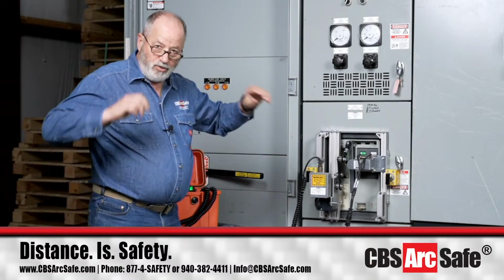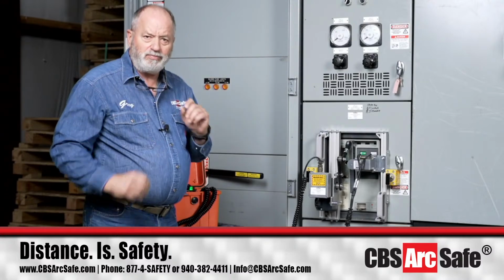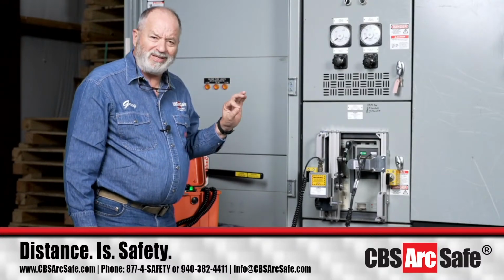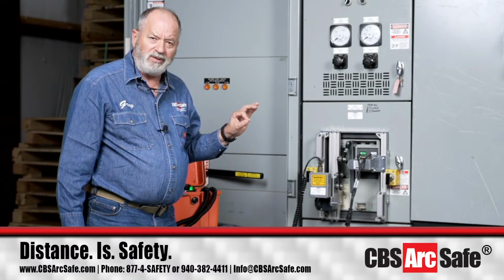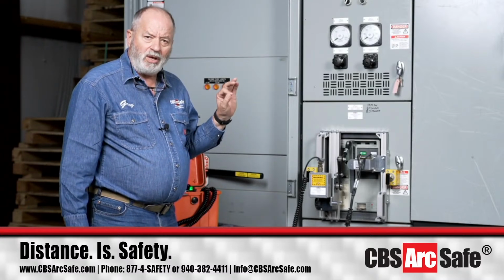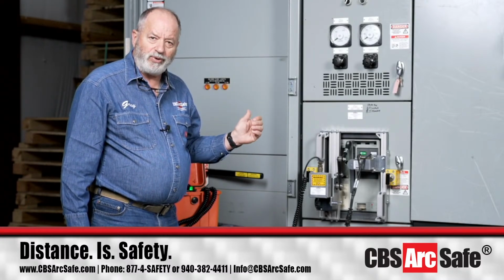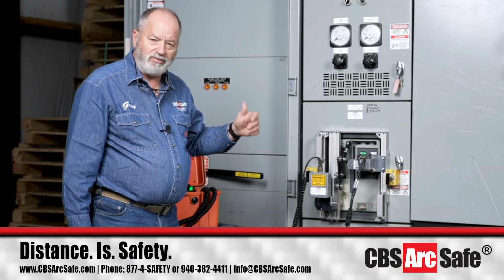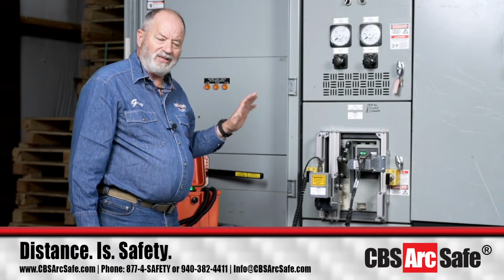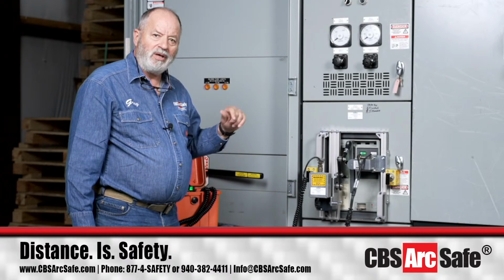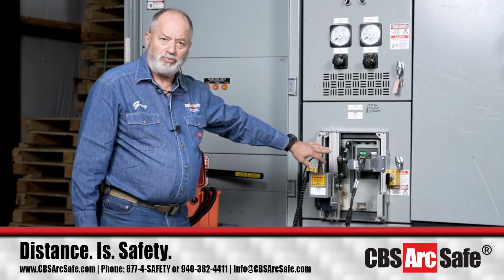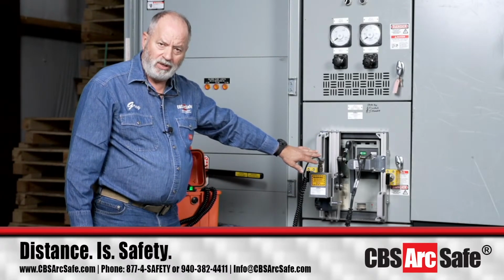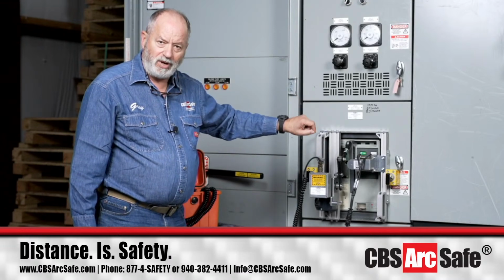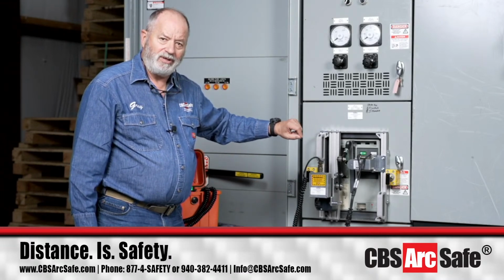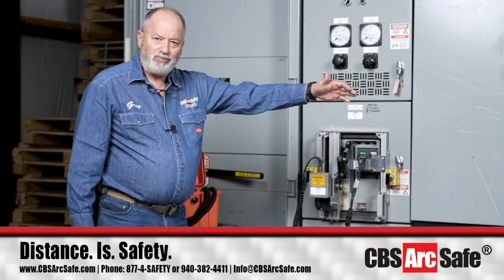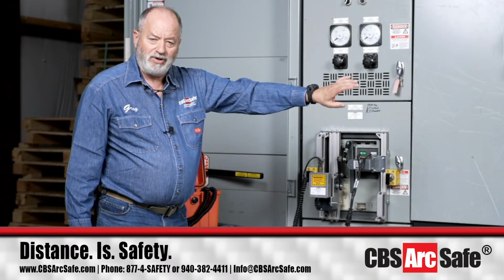The breaker normally takes 5 strokes, but the Eaton literature will tell you it may take up to 7. So one thing to notice: when you're using the RSA-48, if you have a breaker that takes more than 5, reset the system to a single stroke and wait to see that the charging spring actually charges. Then you'd make a note for that cubicle and breaker, like, these first 8 breakers take 5, but this last one takes 7.